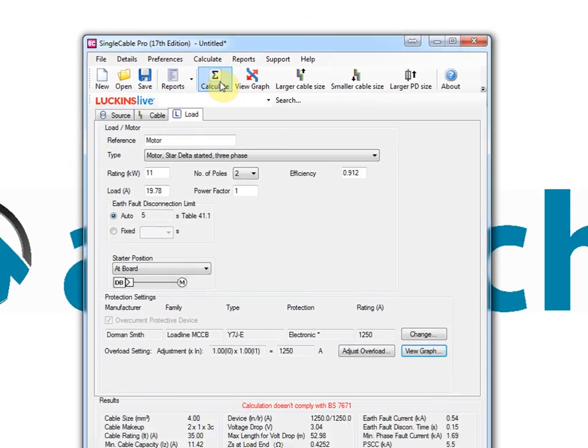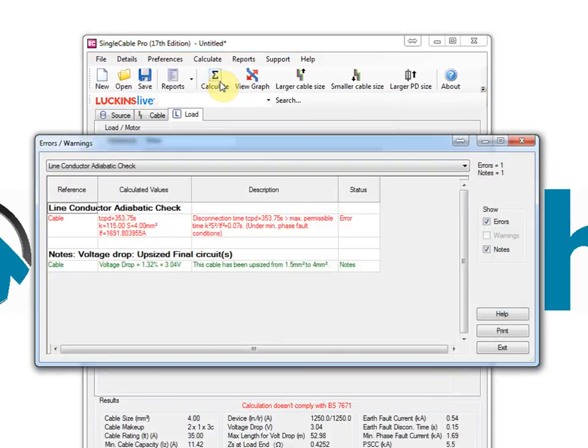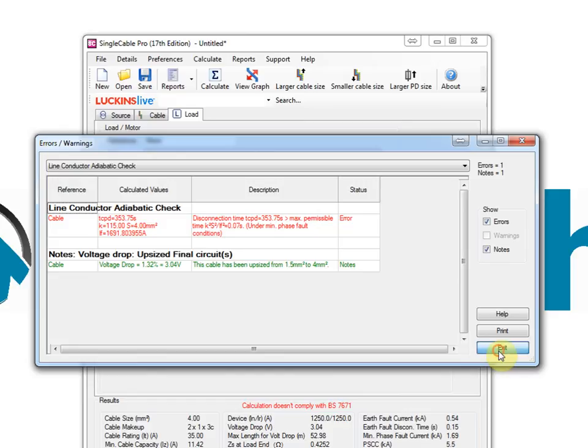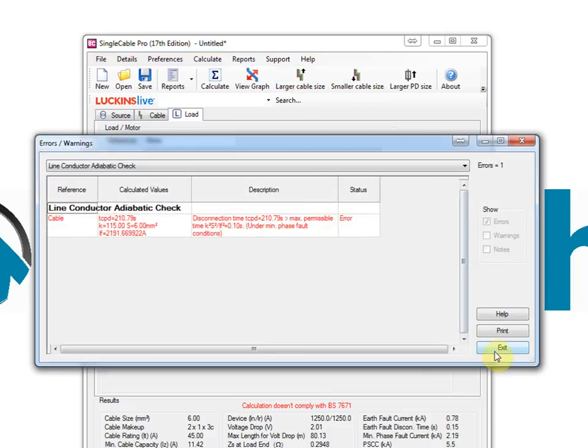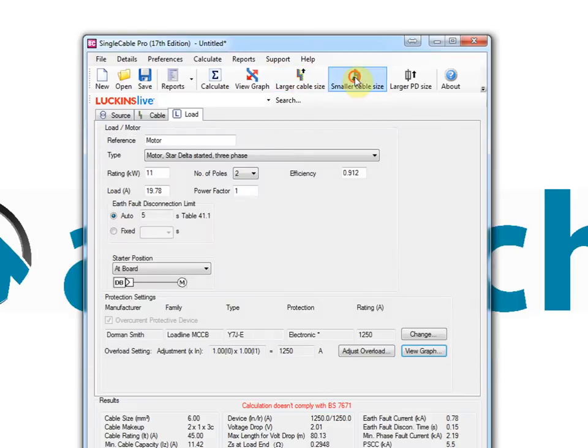Protected device breaking capacity check and volt drop check. Once calculated, the program also enables you to look at the results for the next cable size larger or smaller and the same facility is available for the protective device. This is most useful for looking at what if situations, a luxury not available when doing calculations manually.